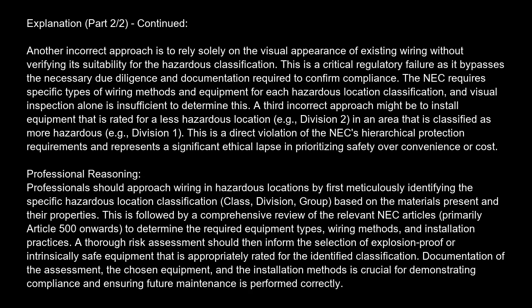Professionals should approach wiring in hazardous locations by first meticulously identifying the specific hazardous location classification, class, division, group, based on the materials present and their properties. This is followed by a comprehensive review of the relevant NEC articles, primarily Article 500 onwards, to determine the required equipment types, wiring methods, and installation practices. A thorough risk assessment should then inform the selection of explosion-proof or intrinsically safe equipment that is appropriately rated for the identified classification. Documentation of the assessment, the chosen equipment, and the installation methods is crucial for demonstrating compliance and ensuring future maintenance is performed correctly.